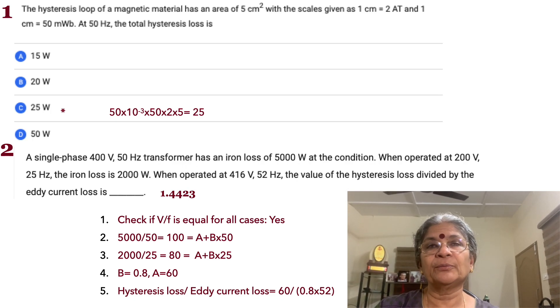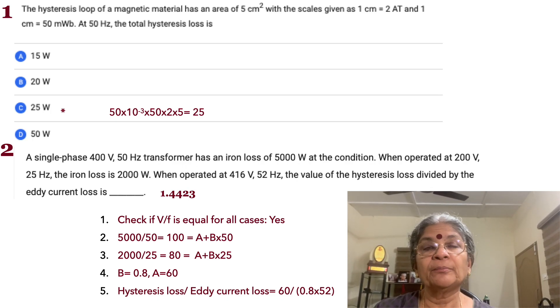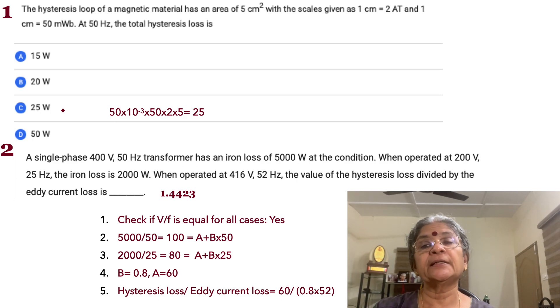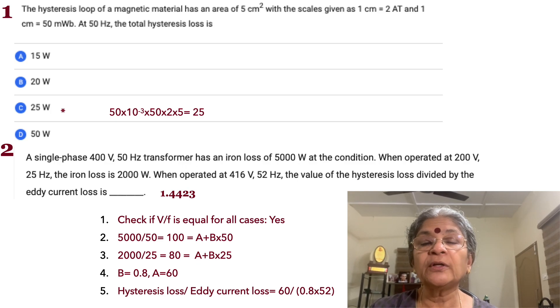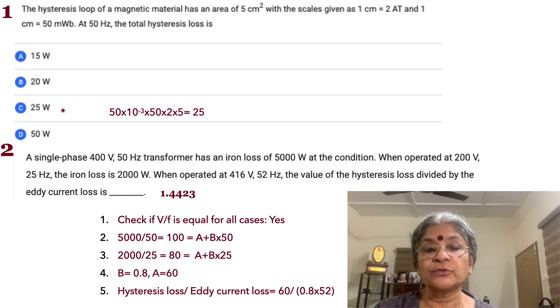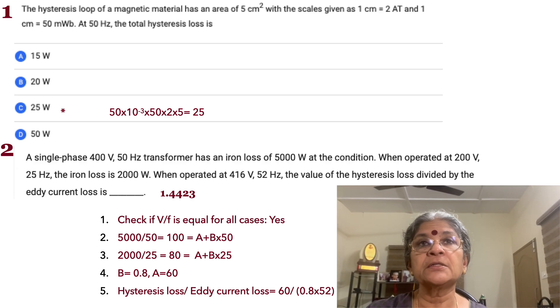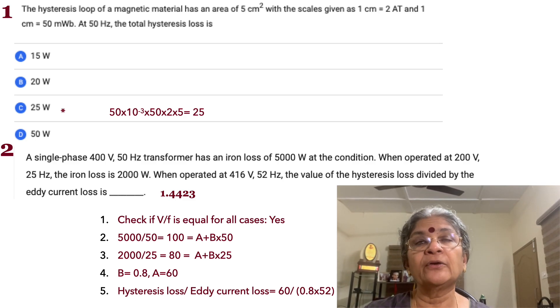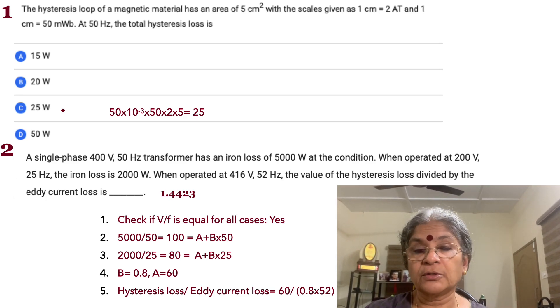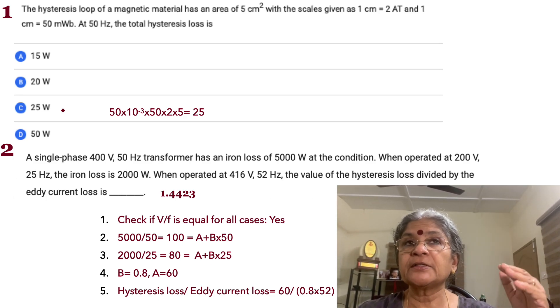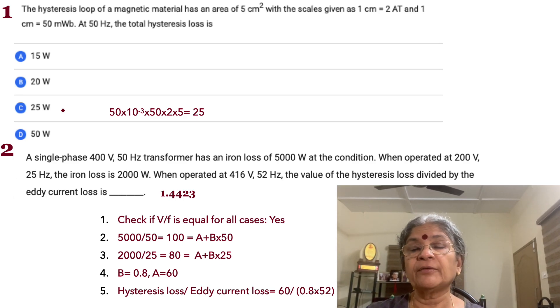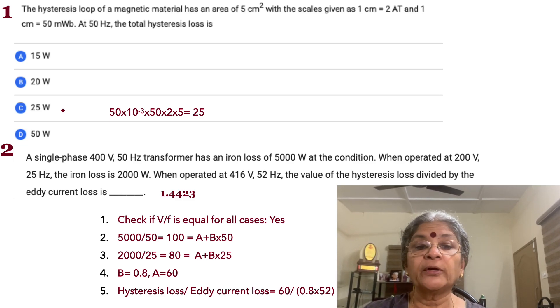Problem 2: a single-phase 400V, 50Hz transformer has iron loss (including both hysteresis and eddy current loss) of 5000 watts. When operated at 200V, 25Hz, the frequency and voltage have both changed. The first check is always whether V/f remains constant — 400/50 equals 200/25, so yes. Iron loss at 200V, 25Hz is 2000 watts, down from 5000 watts.